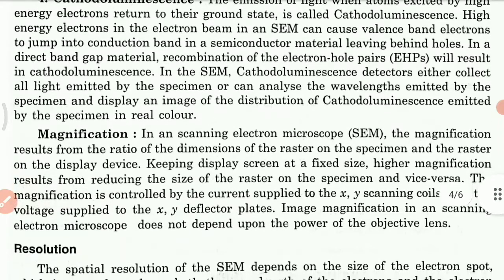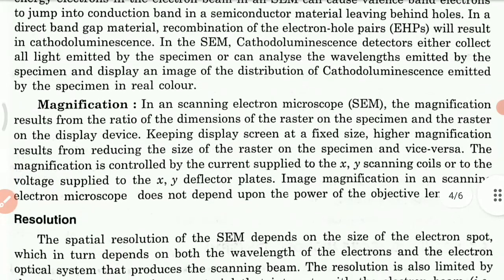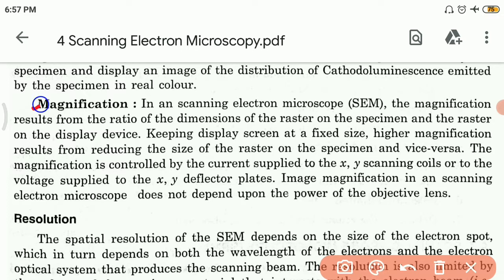Now let us see the magnification or magnifying power of the SEM, that is the scanning electron microscope. The magnification results from the ratio of the dimension of the raster on the specimen and the raster on the display device. Keeping the display screen at a fixed size, higher magnification results from reducing the size of the raster on the specimen, and vice versa.